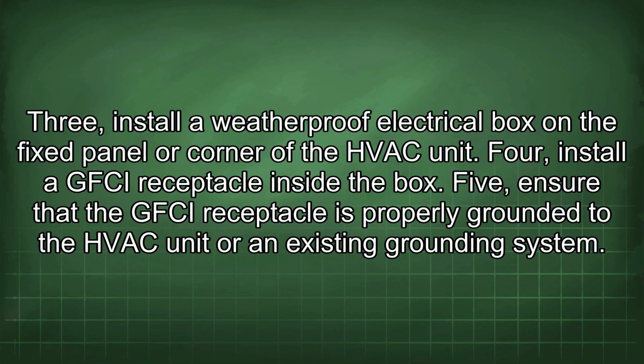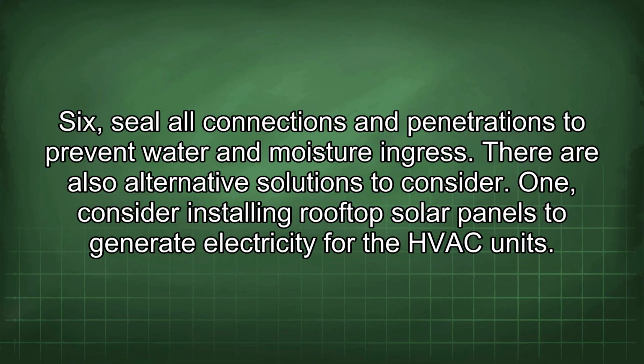3. Install a weatherproof electrical box on the fixed panel or corner of the HVAC unit. 4. Install a GFCI receptacle inside the box. 5. Ensure that the GFCI receptacle is properly grounded to the HVAC unit or an existing grounding system. 6. Seal all connections and penetrations to prevent water and moisture ingress. There are also alternative solutions to consider.